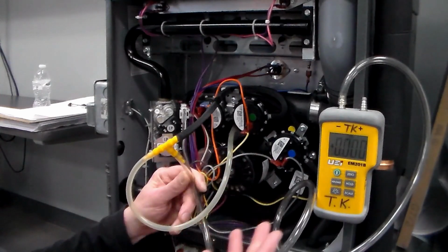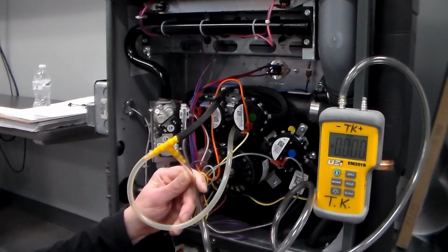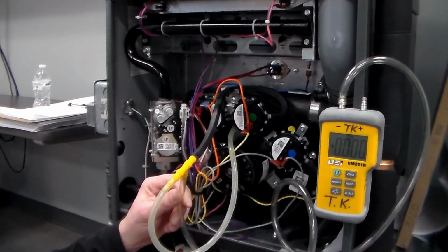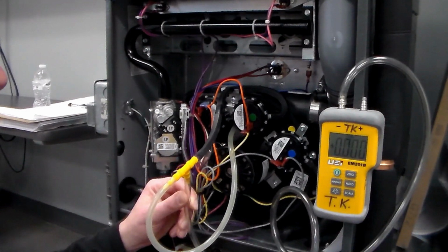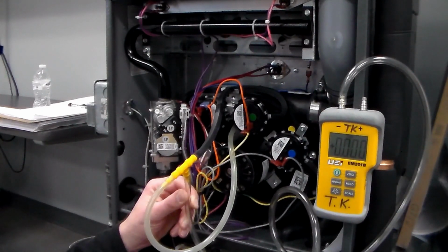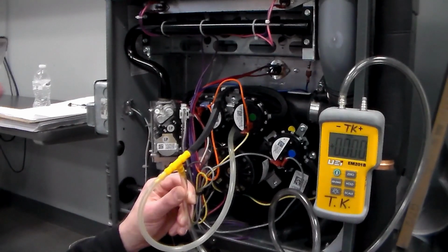Perhaps we've got a plugged flue or a slow condensate drain or a draft inducer issue of some sort. So this is why we want to check this with a manometer or a pressure gauge to verify that that switch is actually seeing the correct draft it should. Now most manufacturers will tell you they want to see at least a consistent 20% higher draft than what this switch is rated at. So if you have a 1-inch pressure switch, for example, you would want to see that draft reading at 1.2. So I have my digital manometer T'd in here.